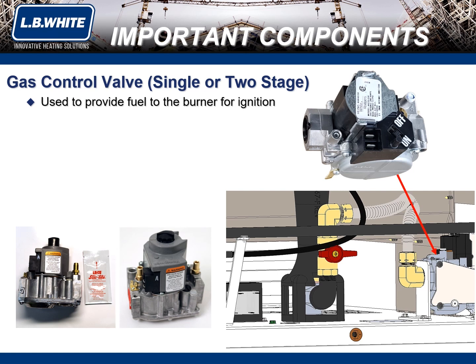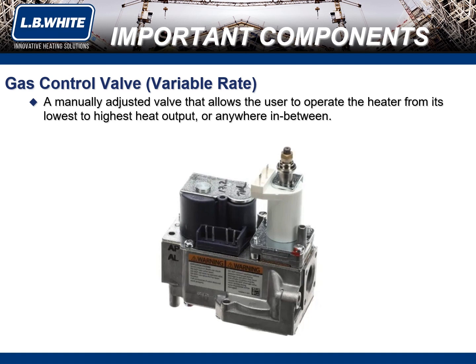So, let's say you have 13 inches water column coming into the heater via your fuel source. It will not actually burn at that. The valve will reduce it down to the 8 inches water column the heater's data plate calls for. A variable rate valve is a manually adjusted valve that allows the user to operate the heater from its lowest to highest heat output or anywhere in between.